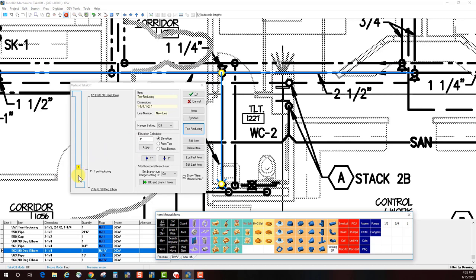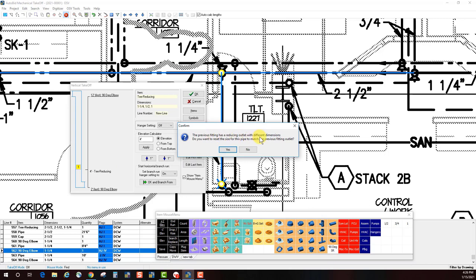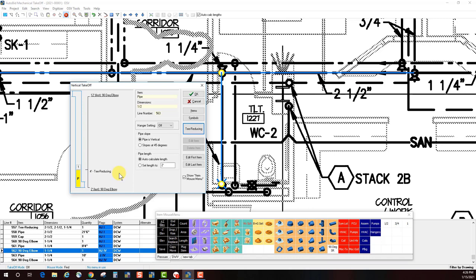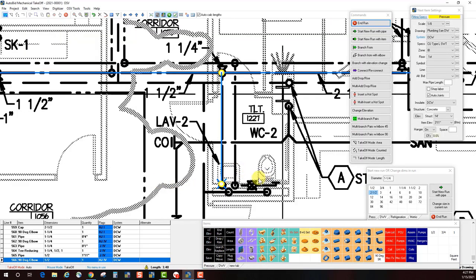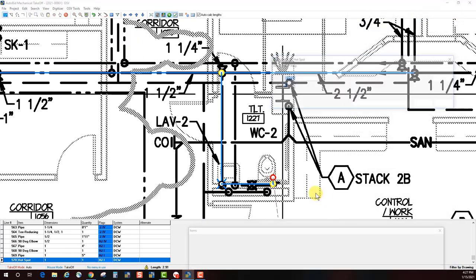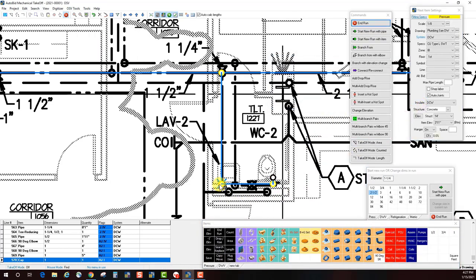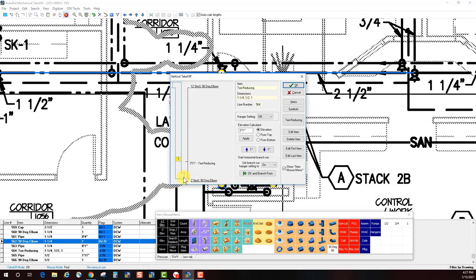Opening the vertical, I need to insert a T to feed the water closet. I use the reducing T button — it prompts for the information: inch and a quarter coming in, half inch feeding down to the lavatory, and one inch in the branch for the water closet. I set the item elevation to avoid placing it right on the elbow. After clicking OK, it inserts the reducing T at the chosen elevation. The pipe below resets to half inch, giving a half inch pipe and 90-degree elbow at the bottom. Using OK and Branch From, I attach to the vertical and run out to the water closet.